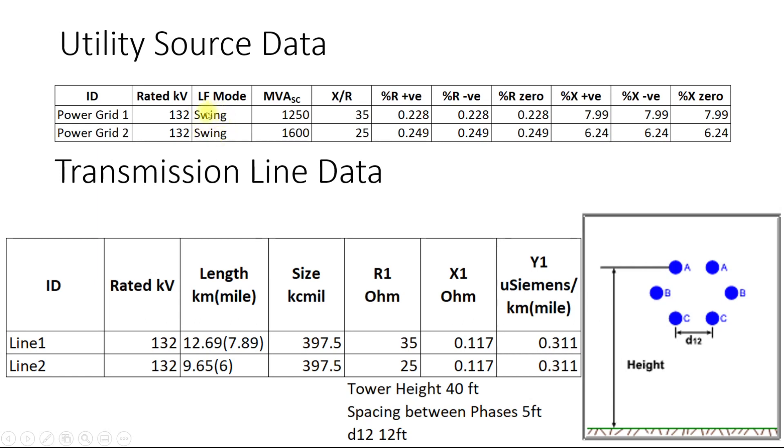Here we are going to have two swing buses for each power grid and then the MVA short circuit capacity X by R rating is given. In ETAP when you put MVA short circuit and X by R these values will be automatically calculated. We will see if we get the same values or not.